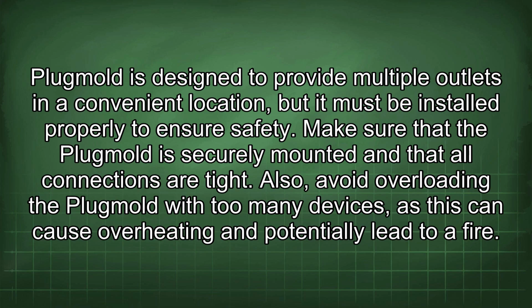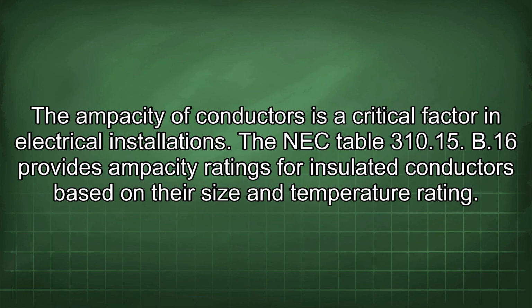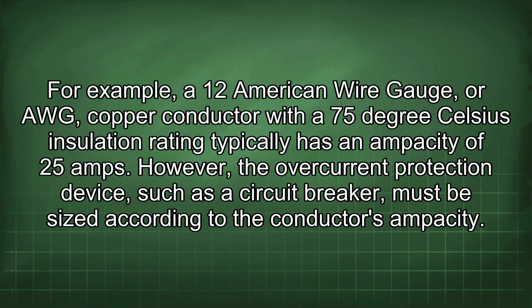Also, avoid overloading the Plugmold with too many devices, as this can cause overheating and potentially lead to a fire. The ampacity of conductors is a critical factor in electrical installations. The NEC Table 310.15(B)(16) provides ampacity ratings for insulated conductors based on their size and temperature rating. For example, a 12 American Wire Gauge, or AWG, copper conductor with a 75 degrees Celsius insulation rating typically has an ampacity of 25 amps.